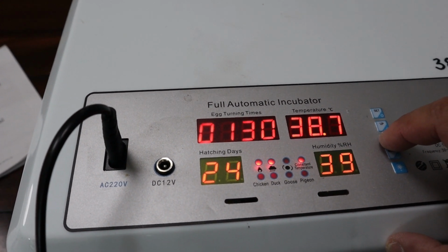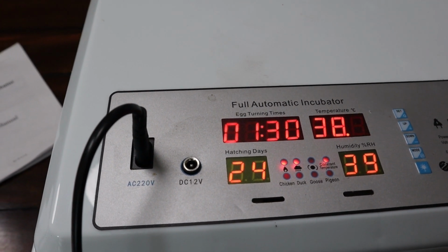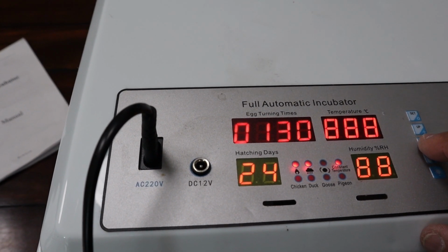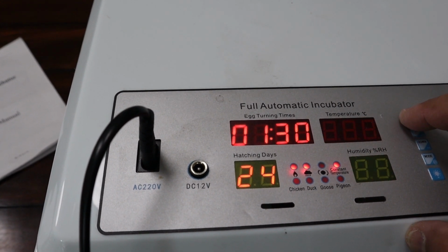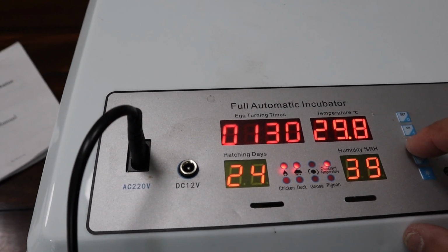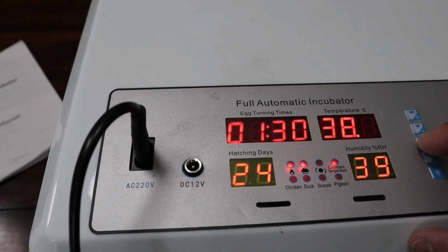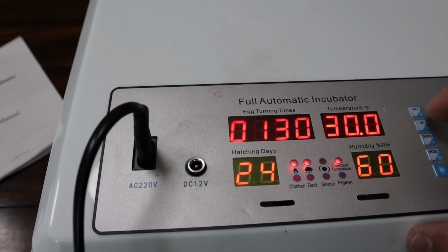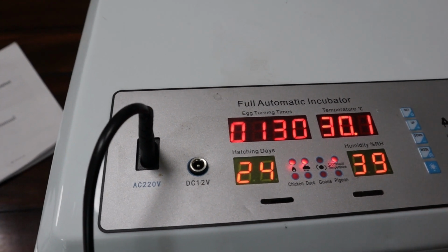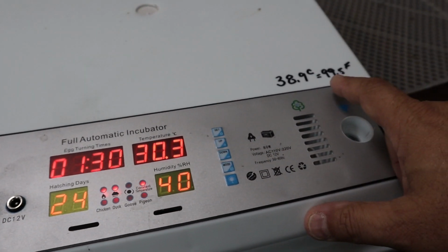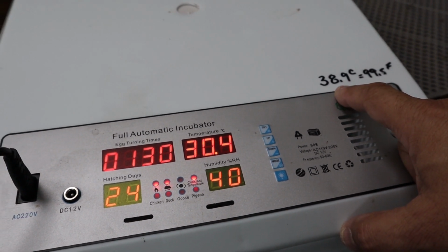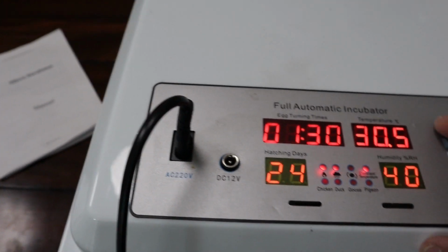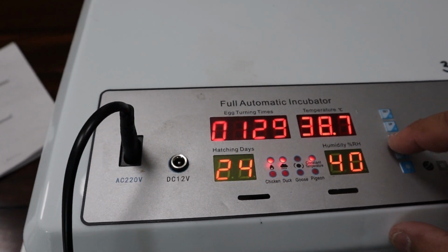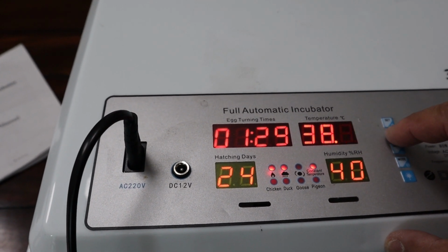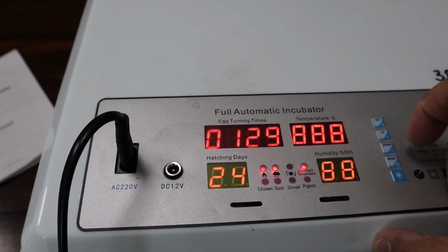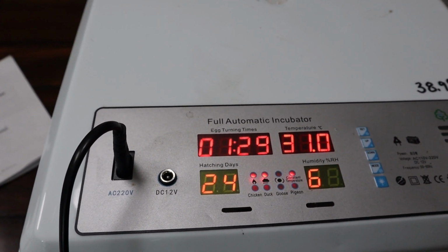So what we did after our calibration is we realized that to get to 99.5, we've got to be at about 38. We need to be at 38.9. So we're going to go ahead and set it. To get to 99.5 degrees, we've got to set this unit at 38.9. So we're going to hit the set button, increase it to 38.9, hit the set button again, and it will store that temperature.